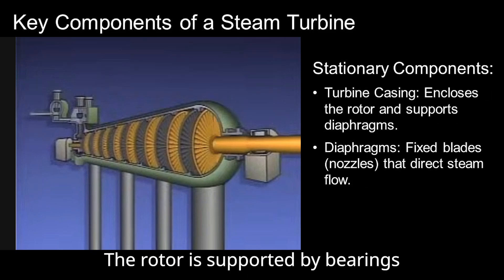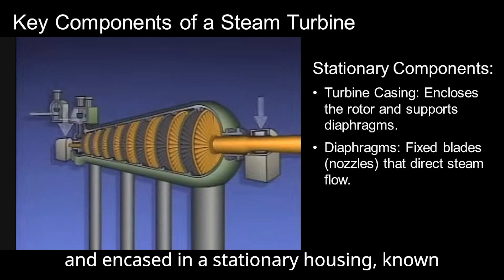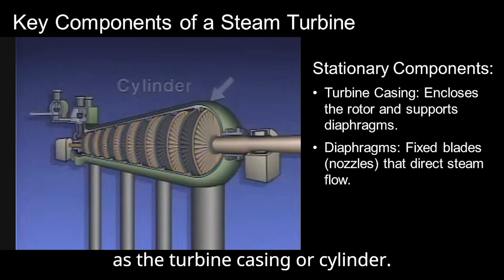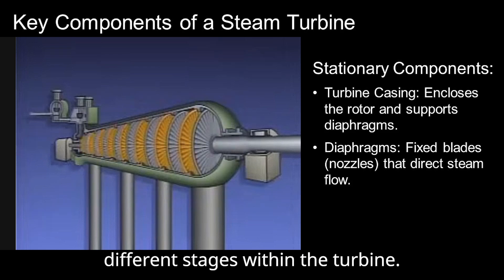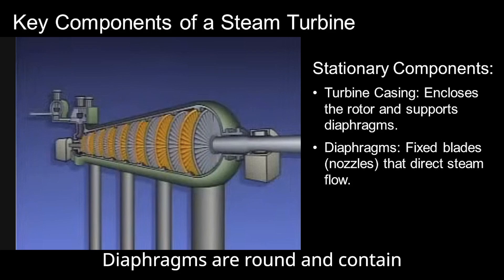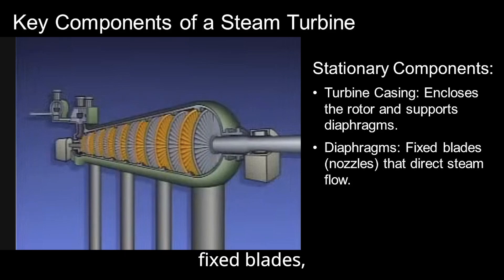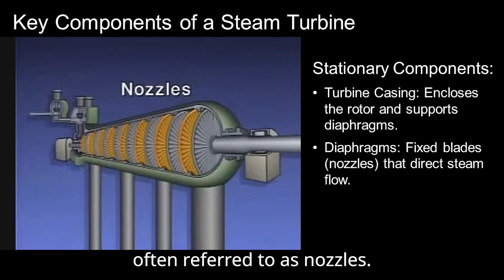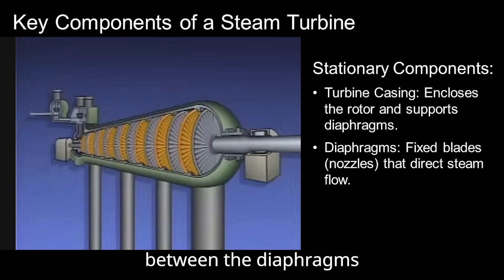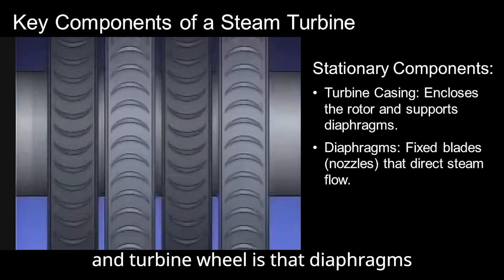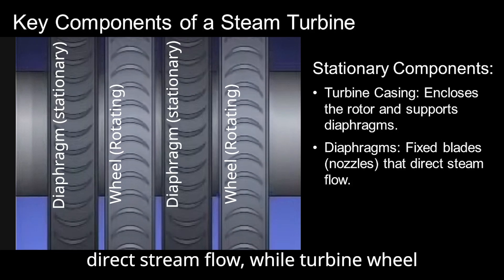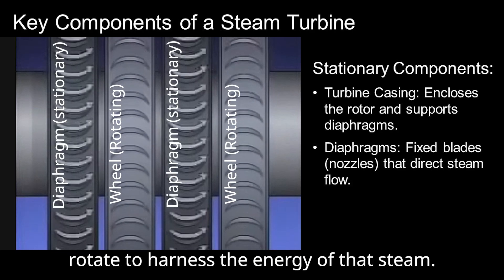The rotor is supported by bearings and encased in a stationary housing, known as the turbine casing or cylinder. This casing houses the diaphragm, which separates different stages within the turbine. Diaphragms are round and contain fixed blades, often referred to as nozzles. The key difference between the diaphragms and turbine wheels is that diaphragms direct steam flow, while turbine wheels rotate to harness the energy of that steam.